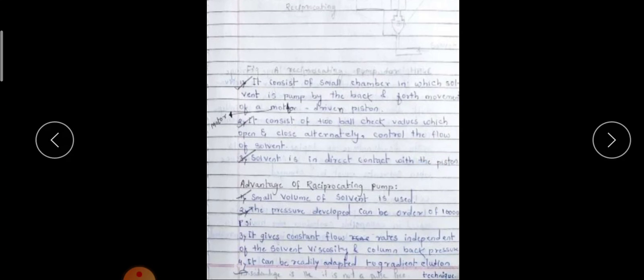The reciprocating pump consists of a small chamber in which the solvent is pumped by the back-and-forth movement of a motor-driven piston. It consists of two ball check valves which open and close alternately to control the flow of solvent. Advantages: small volume of solvent is used, pressure developed can be of the order of 10,000 psi, it gives constant flow rates independent of solvent viscosity and column back pressure, and it can be readily adapted to gradient elution technique.